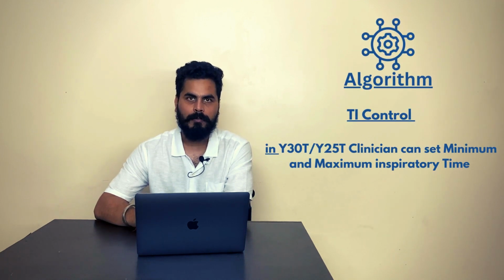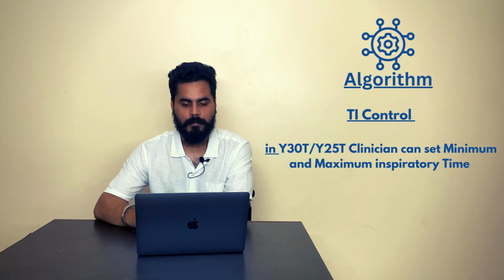Then there is a leak compensation option available as well. When you're using PAP therapy with the mask, there are chances of unintentional leaks, and the BMC Y30T is capable of compensating for the leak to make therapy more effective. TI control is there. TI means inspiratory time control, which lets you adjust inspiratory time by choosing minimum and maximum limits.